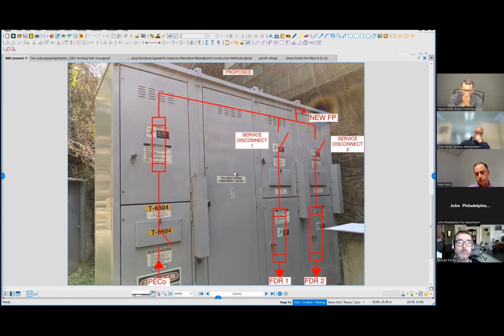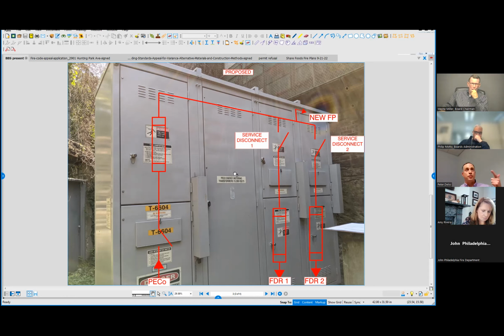Peter, you're saying the code requires it to be ahead of the service disconnecting means to eliminate any of these possible failures. Because as we know, if this switch is opened up for preventive maintenance, predictive maintenance, or somebody has to do something to it, it blows up. I mean, we have preventive maintenance, predictive maintenance, and an explosion, a fuse failure. That's where all that stuff is eliminated. If we tap ahead, that's why it says in the code it shall be directly ahead of the service disconnecting means, to eliminate all that. Like I said, as soon as I saw it, I flagged it.